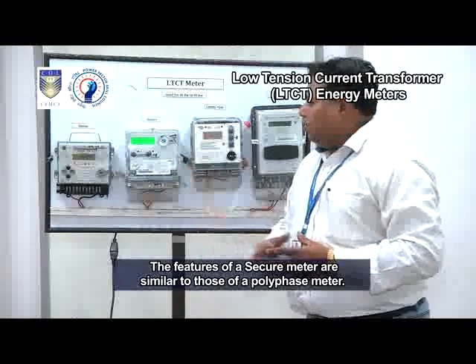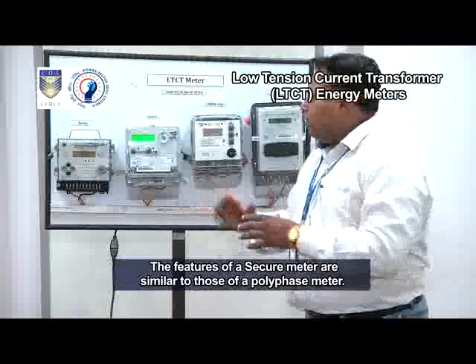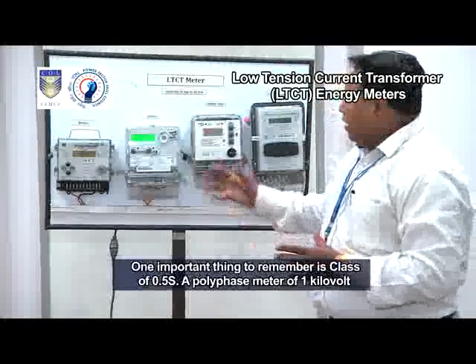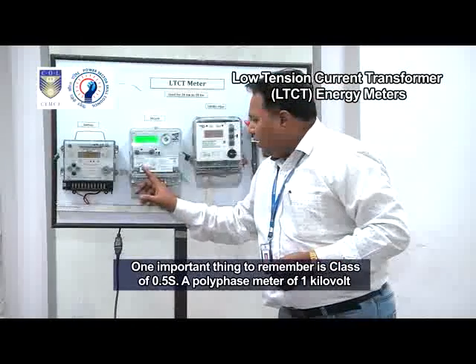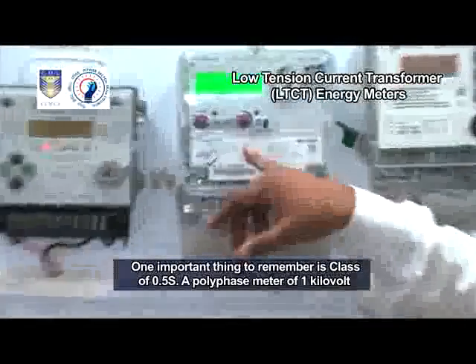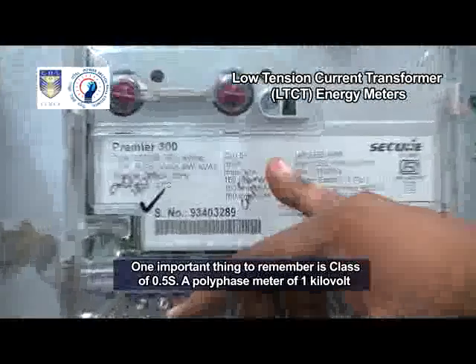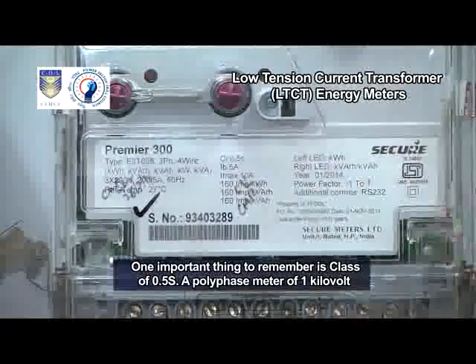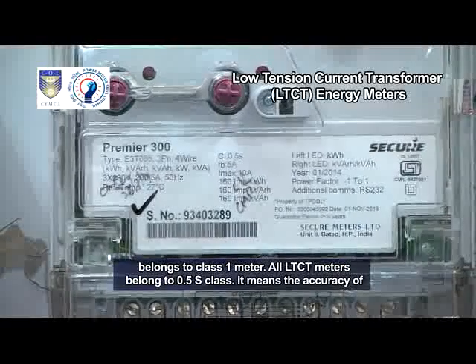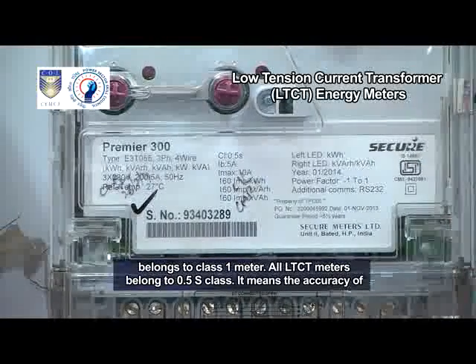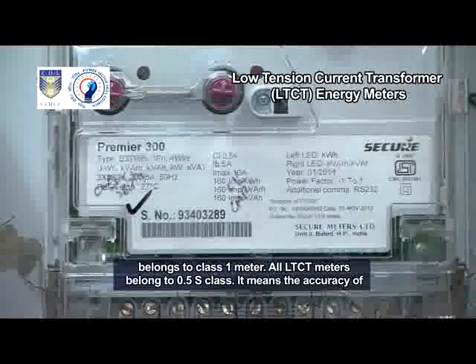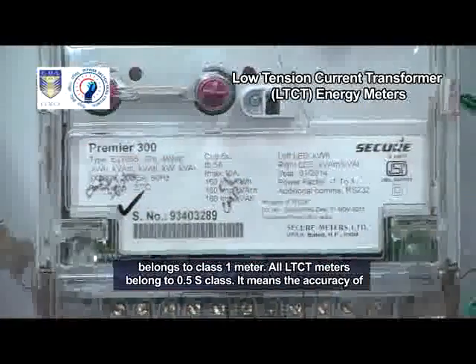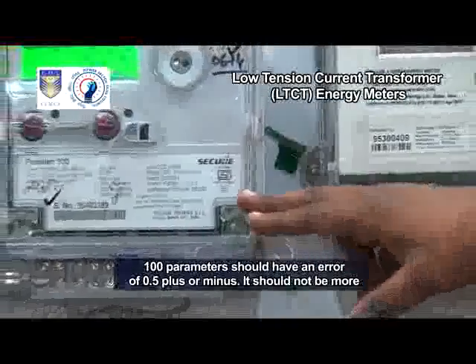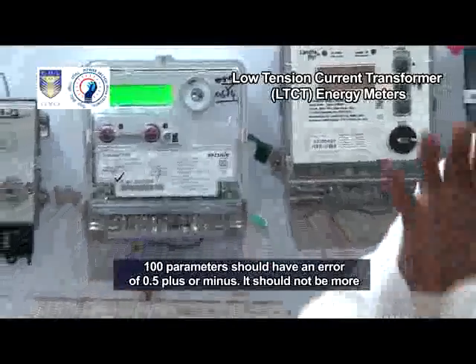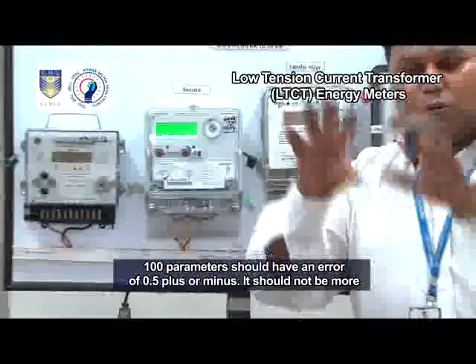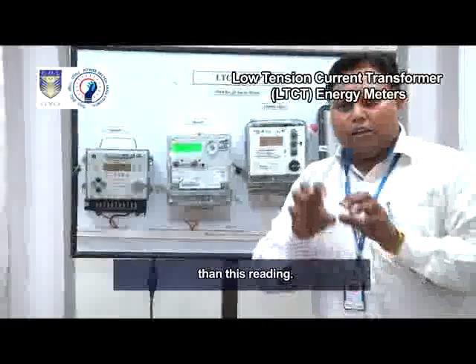The features of a Secure meter are similar to those of a polyphase meter. One important thing to remember is class 0.5 S. A polyphase meter of 1 kilovolt belongs to class 1 meter. All LT-CT meters belong to 0.5 S class. It means the accuracy of all parameters should have an error of plus or minus 0.5. It should not be more than this reading.